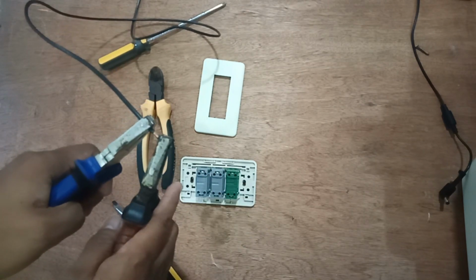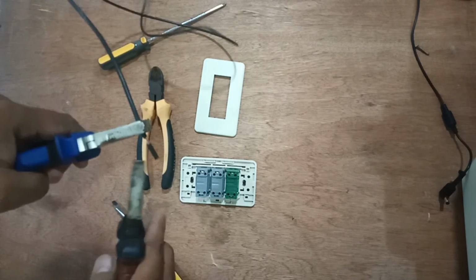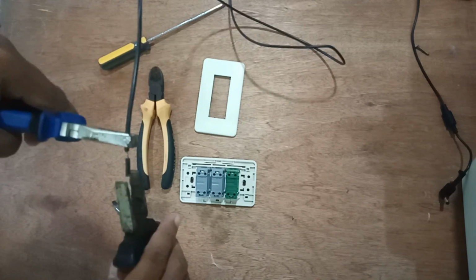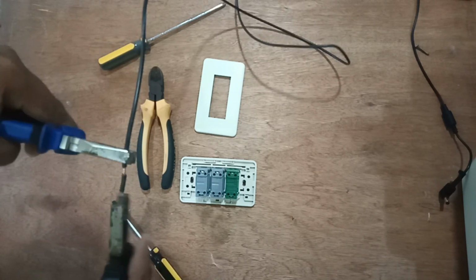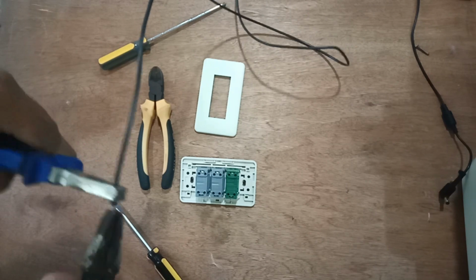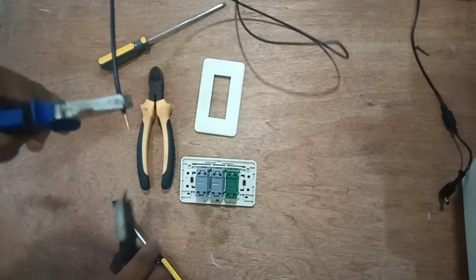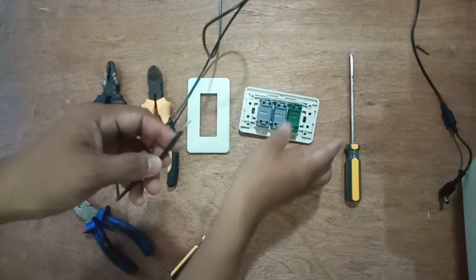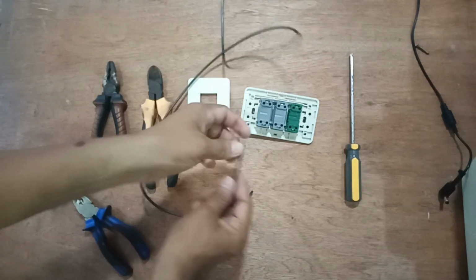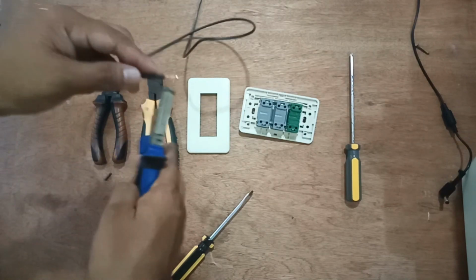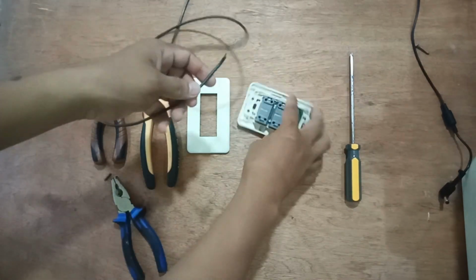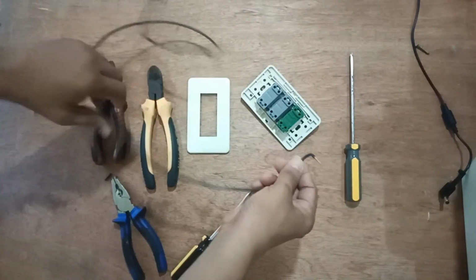Do not remove the insulator all the way. All you have to do is twist first the parted insulator, and then slowly push it out, to jumper the 3-gang single pole switch. Of course, we have to estimate first where we are going to jumper the wire like this.